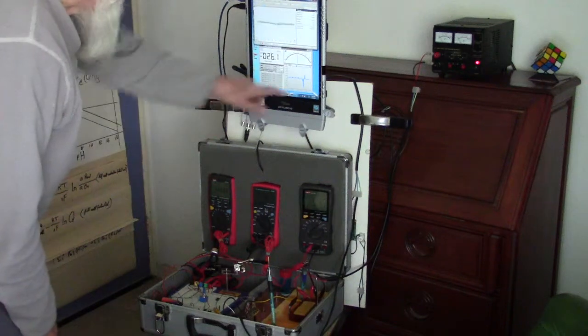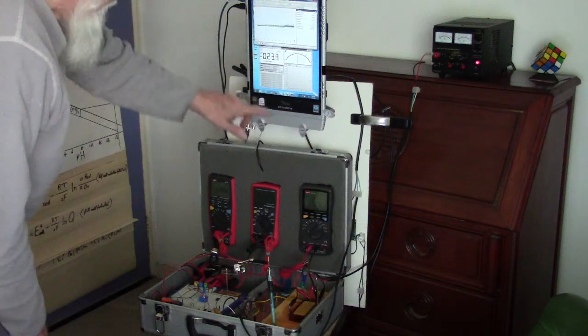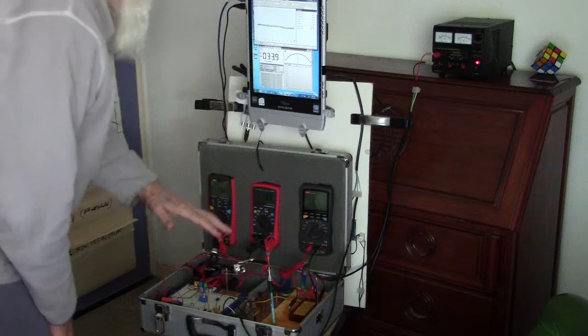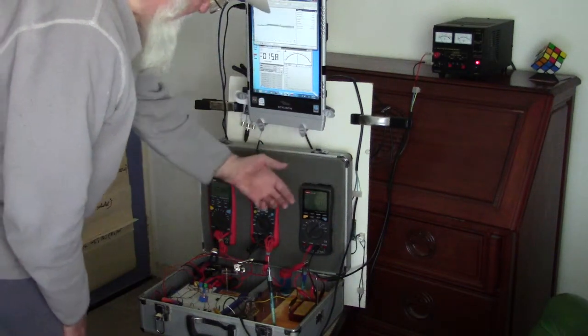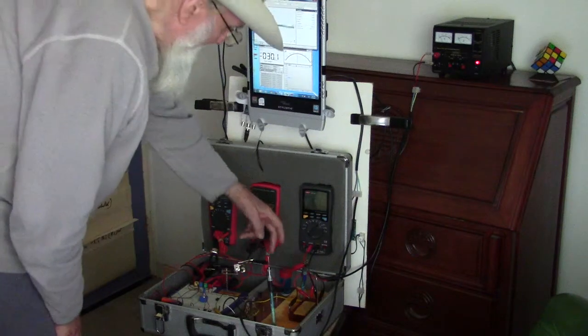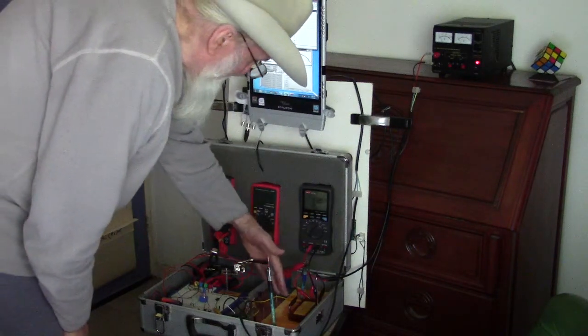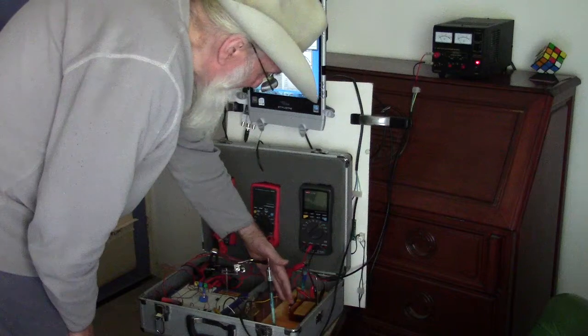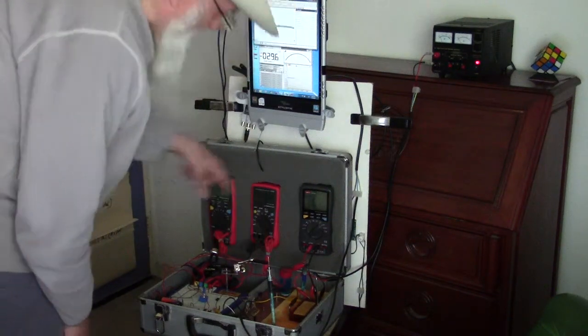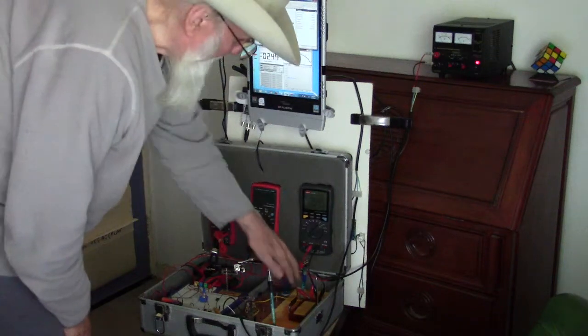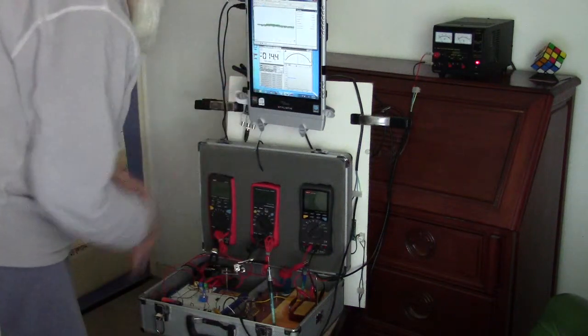And you can see that both of the electrodes are out of the influence of the switching of the cathodic protection system. Now the reason for that is that the connection to the cathodic protection system is here through the Alexander cell to the pipeline. And the plates on the bottom of the Alexander cell complete the circuit.